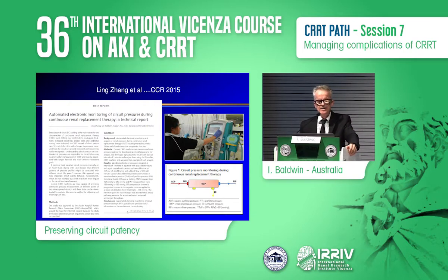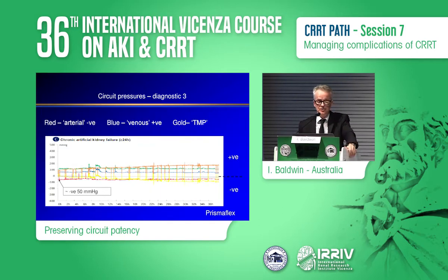So Ling Zhang from China and I did some further work on this looking at pressures, and this is the sort of thing you see on the screens of the modern machines now, quite easily displayed. We understand, the colours there represent, as I've indicated, a circuit beginning a treatment, and the negative pressure, say minus 50, and it's minus 50 in this graph up to 36 hours and beyond.